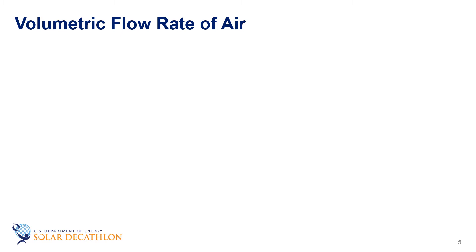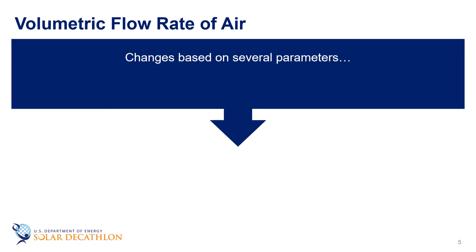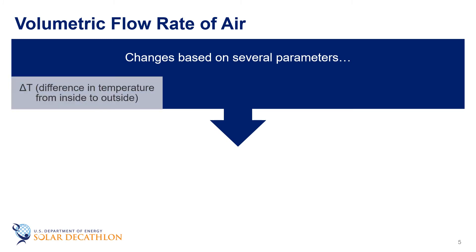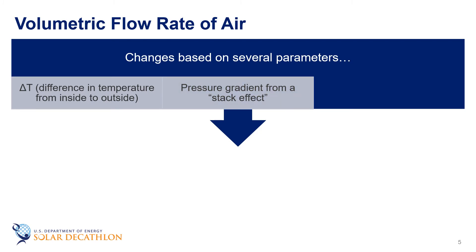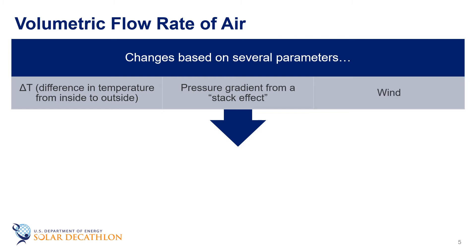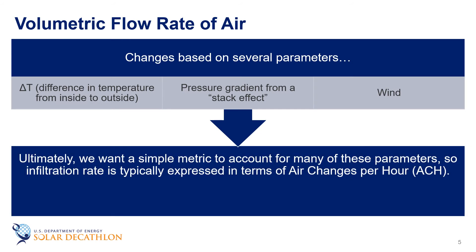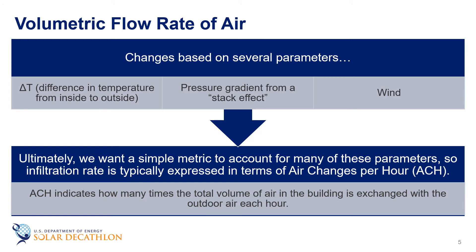As you can imagine, the volumetric flow rate of the air changes based on several parameters, including the change in temperature from inside to outside. You have what is called a stack effect. That is, air moving up through the structure and pressurizing the upper part of the structure, while drawing air in through the lower part of the structure. Wind also has an impact on the amount of infiltration that occurs in a building. That wind can be impacted by surrounding landscaping or other buildings. At the end of the day, we want a fairly simple number that can account for many of these things, and so we often talk about the infiltration rate, and we measure that rate typically in air changes per hour. That is how many times the total volume of air in the building is exchanged with the outdoor air each hour.